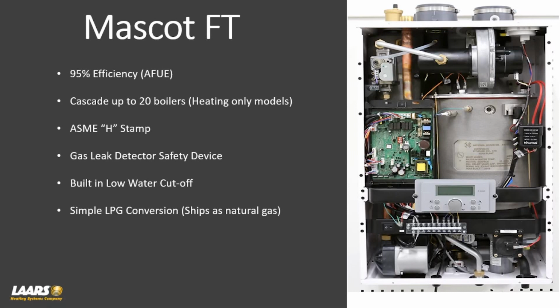Very simple propane conversion. All of these boilers are going to ship natural gas, and we'll give you a propane orifice in the box. This is probably the simplest product to convert to propane to market. Up here, this is a 140. This is the air fuel mixing station prior to the suction side of the blower. And in behind this brass fitting is an orifice. So you would remove this fitting, pull the orifice out, put a new one in, and then we'll talk about dip switches. You just throw the dip switch to propane, and that's it. So this boiler can be converted to propane in less than 4 minutes.